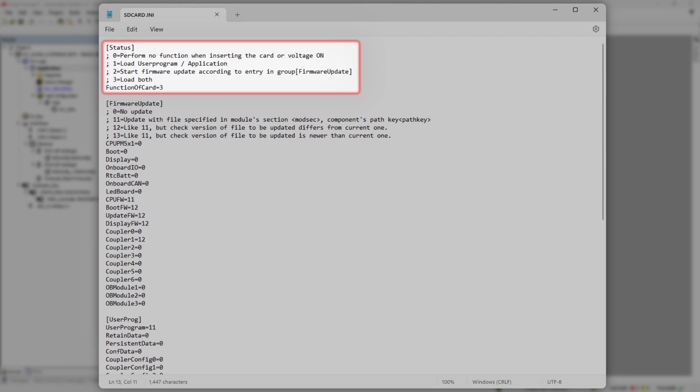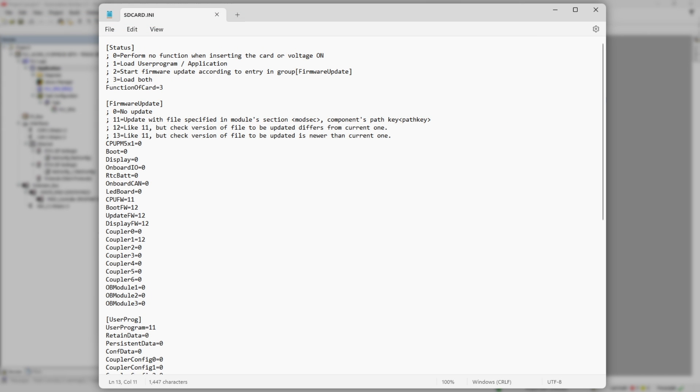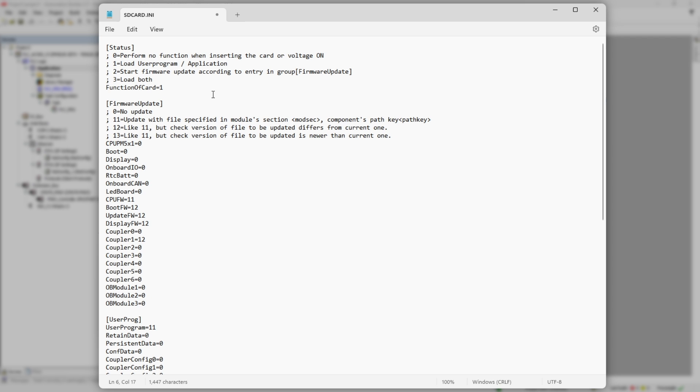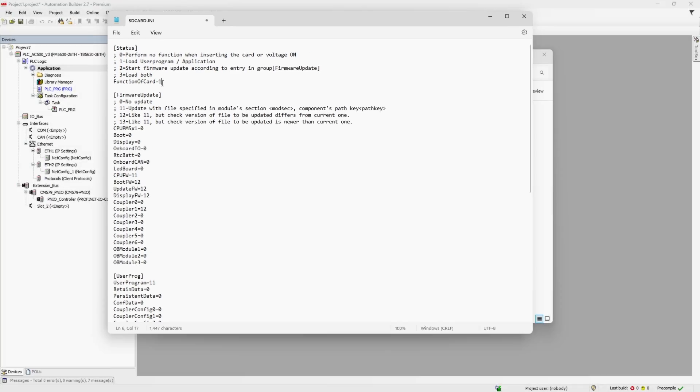Section status is the reason why we even opened this file in the first place. Parameter function of card defines the action PLC will perform during update process. Value zero: no action will be performed. Value one: only user application or boot project will be updated. Remember I told you we'll come back to this topic. That's actually how you do it.